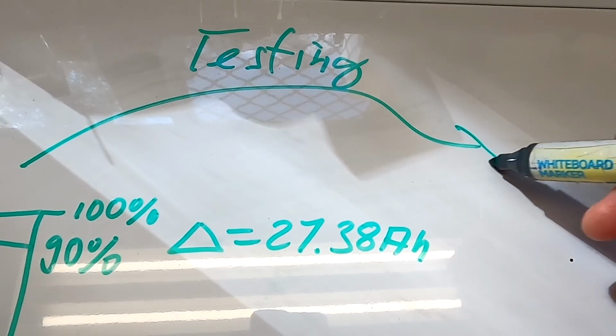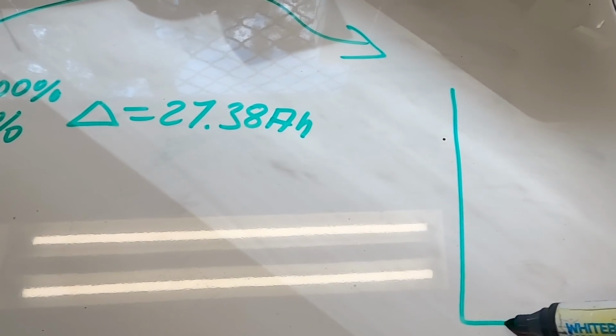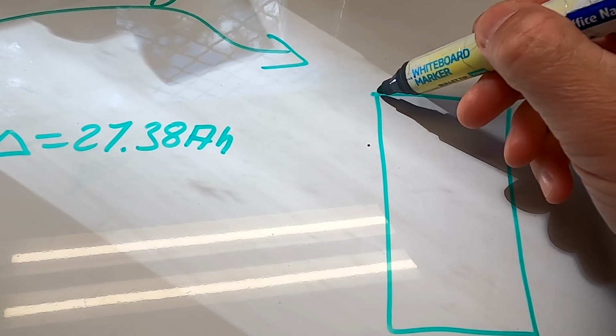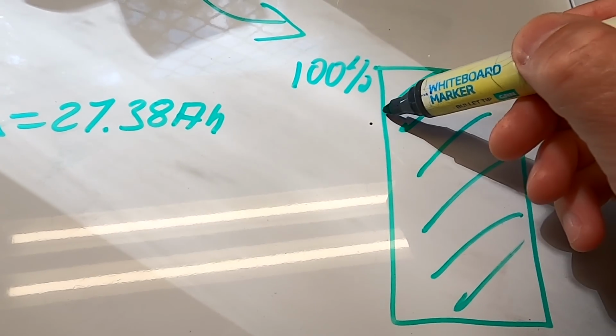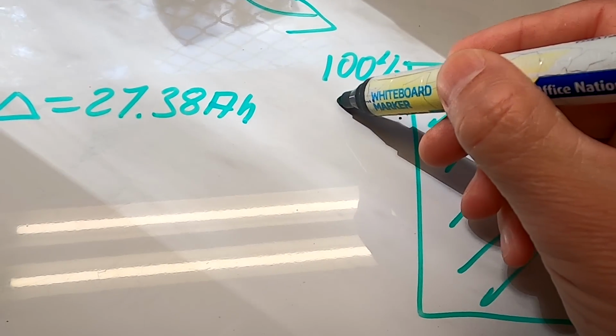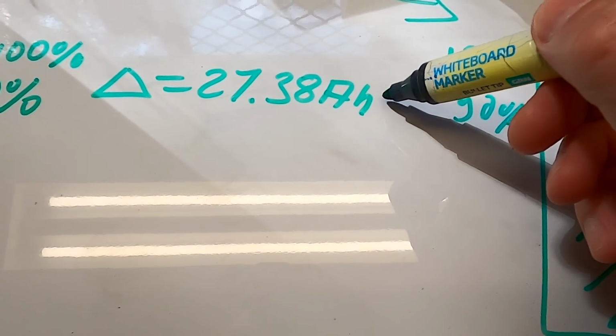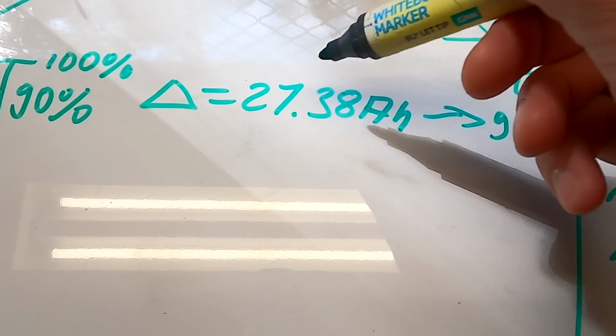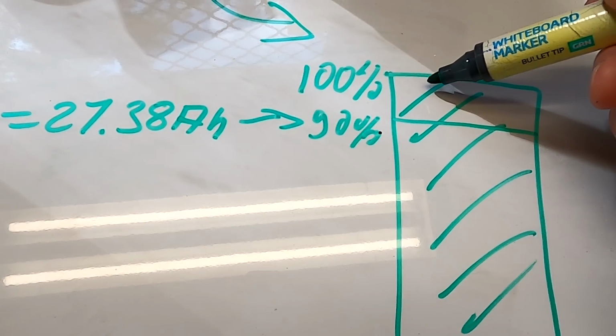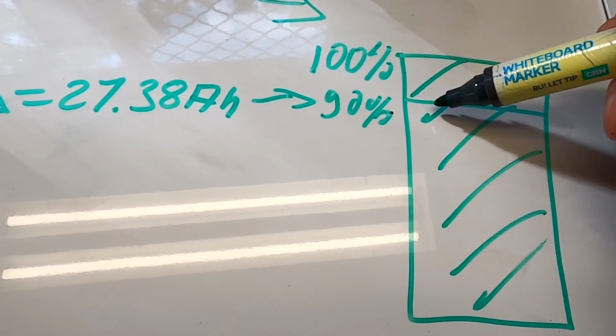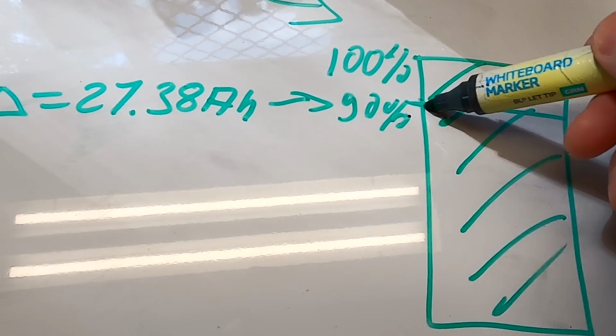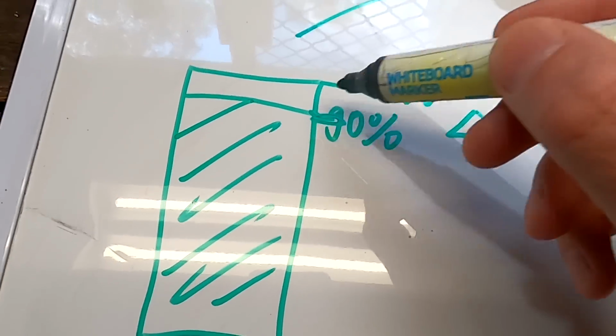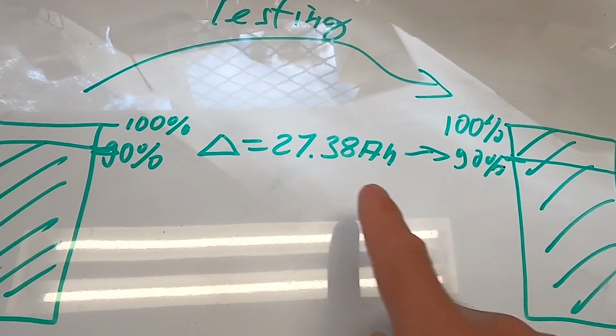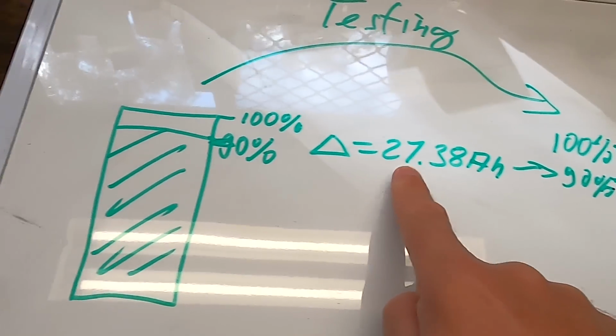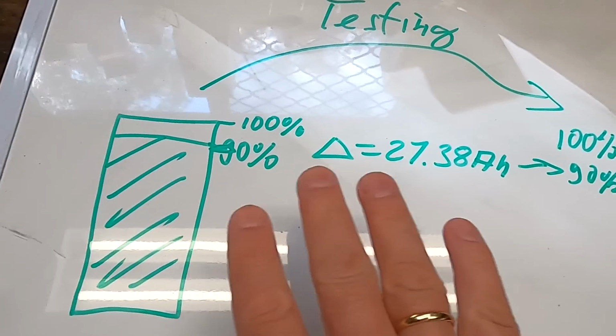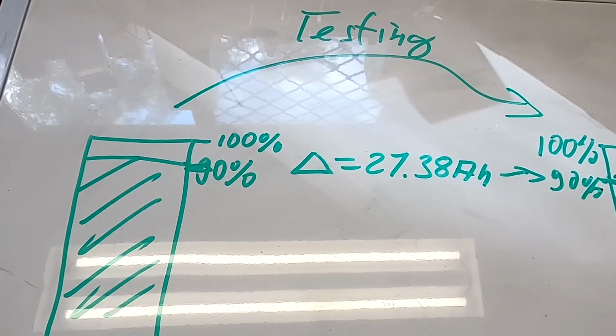Now we've done all the testing, so we need to bring this battery, which is at 100% now, back down to 90%. So we need to take away these 27.38 ampere hours again from this state of charge, and then we should be at the exact same point as we started before our testing. That's why I'm taking this away, to bring the battery back to the same level as all the other batteries.